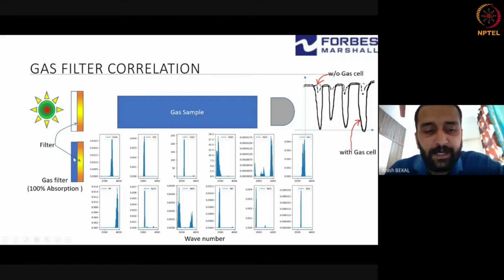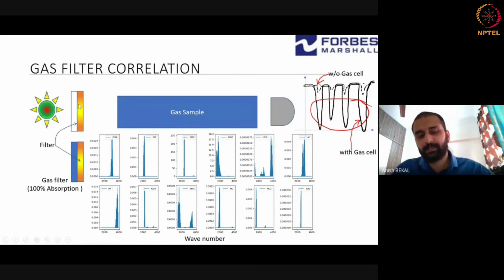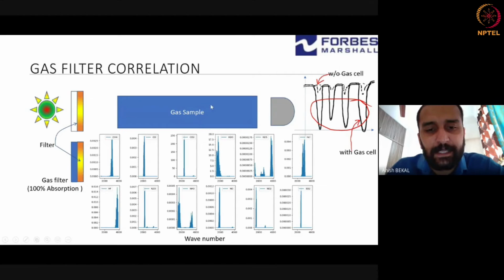There will be an optical filter to isolate the wavelength that you want, but it also has a filled gas in it. So now when the light passes through this filled gas, irrespective of what gas exists in this region, it is going to have a very, very high absorption, like what is shown in this part. So your gas absorption basically gets completely nullified, because there is a very huge absorption of that particular gas in this region, and that you call a reference. Then you have a wheel kind of arrangement where you take off the filter and pass the light directly through the sample. Now you will get the measurement of absorption from the sample itself.